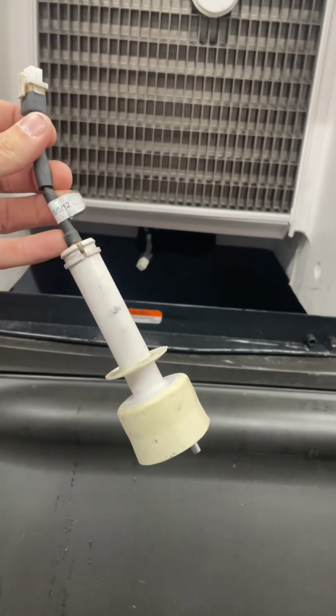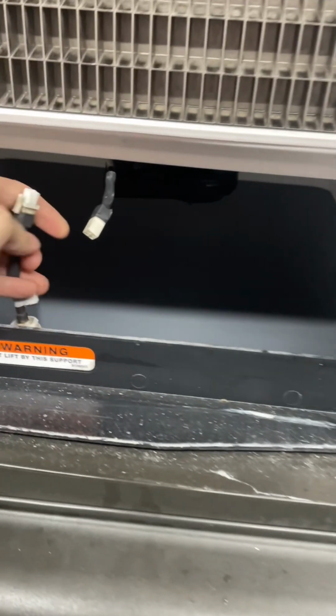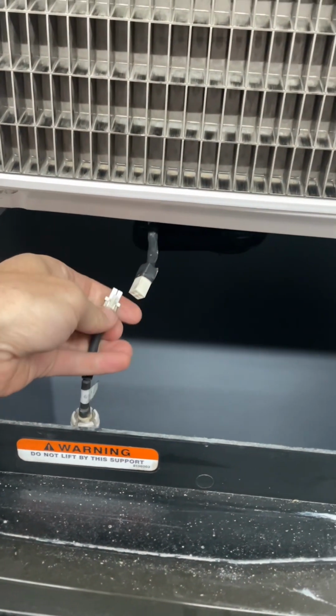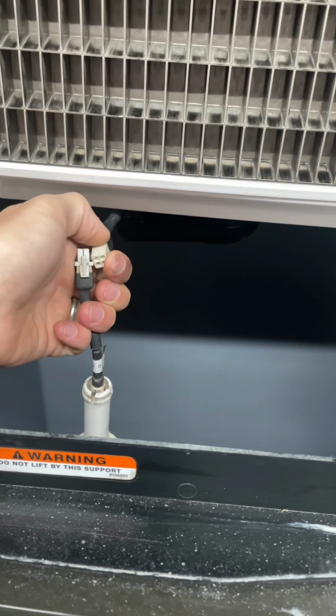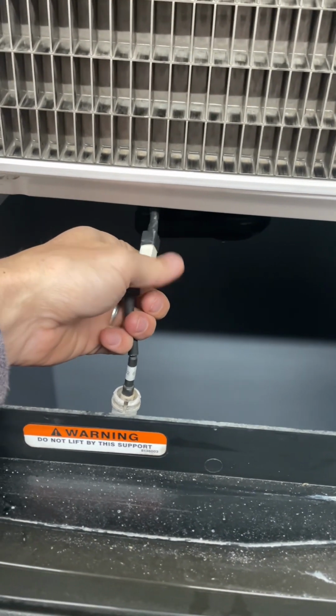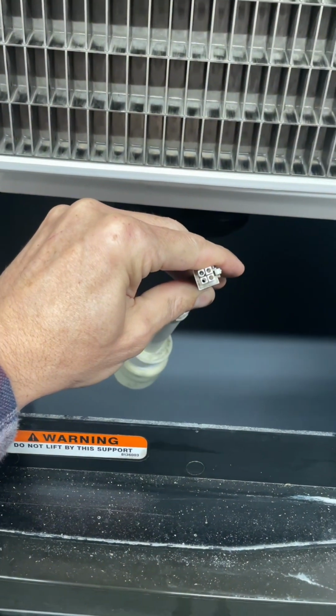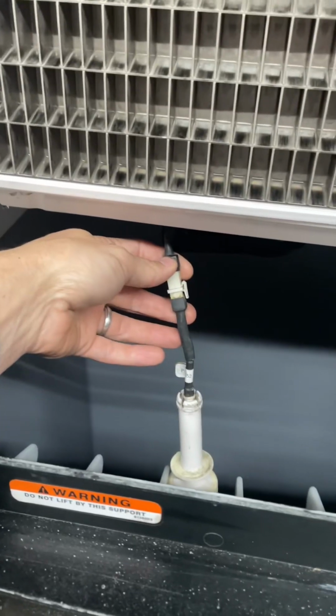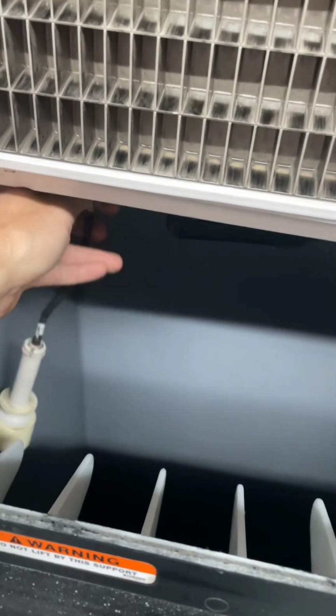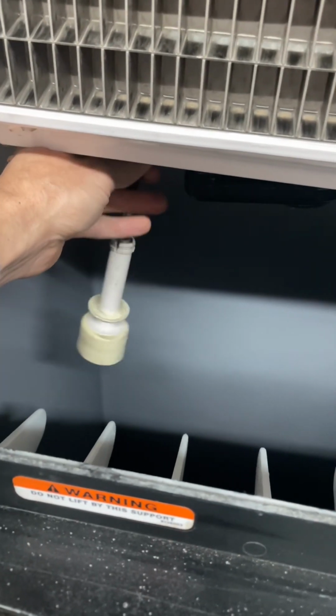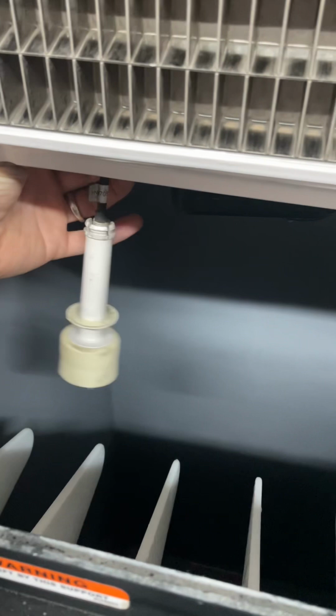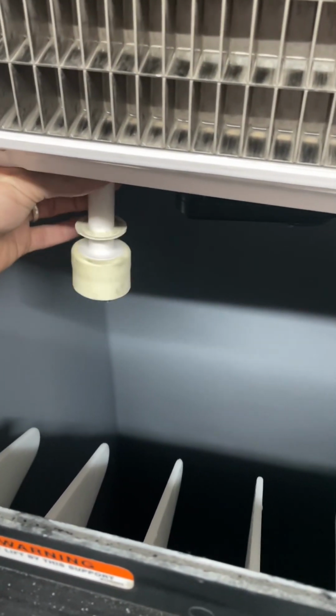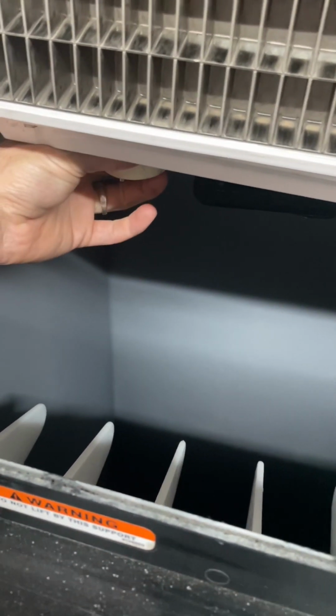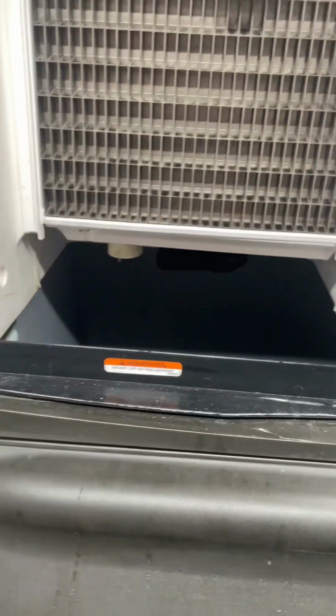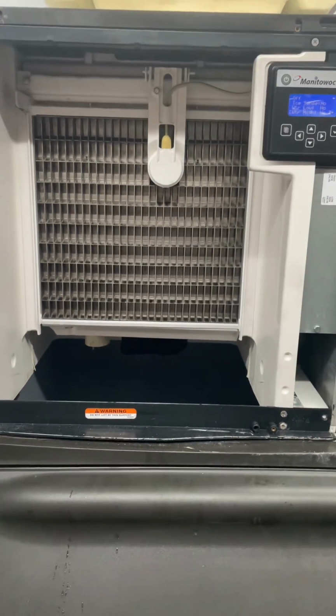To install this, you just do it in reverse order. Make sure that when you plug this in, you line up the clip to the notch here, and that it goes in nice and straight so you don't end up bending any of those metal prongs in there. Once you have it plugged in, you're just gonna feed the cable up and into the ice machine. It should go nice and smooth. Let's see, there we go. And then just until it clicks, and then put your water tray back in and your water curtain and see if your problem is fixed.